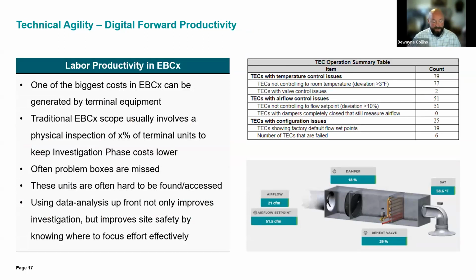One of the biggest costs in almost every single existing building commissioning, or any commissioning for that matter, is the terminal units, right? You can have several hundred of these on a site at a time. And oftentimes the way these are scoped out is that we'll physically inspect a random percentage of those boxes on site, and that can be anywhere from 10 to 20%. What that yields, though, is often those boxes are missed - the ones that have some impact, outside of anecdotal stuff, right? You're going to have people in the space that will say this is a problem, or it's never cool enough in here. But we can be more efficient with that.